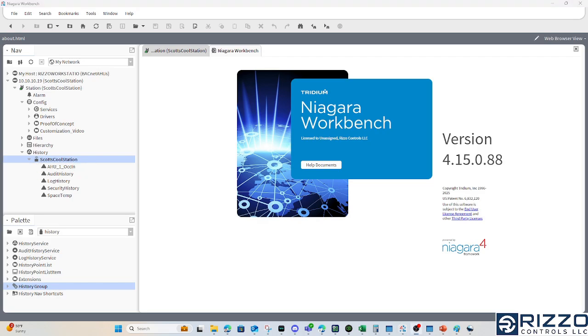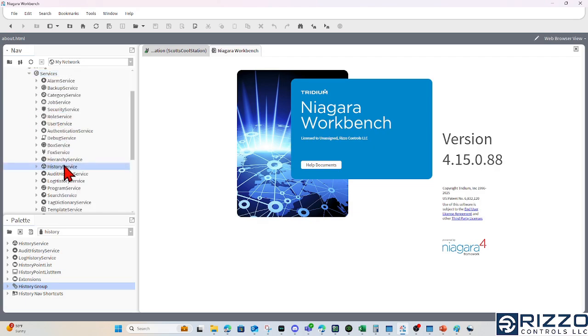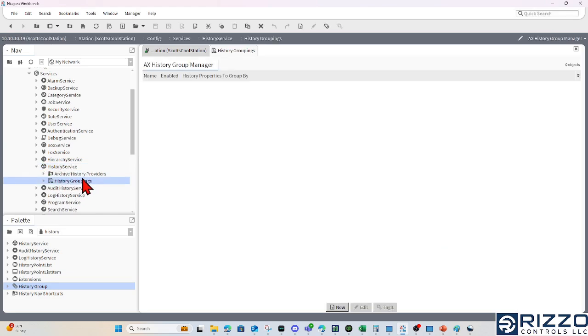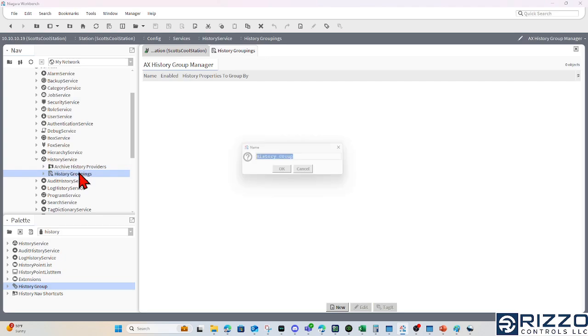So where I'll begin in this video is first creating a history group. I'll expand my services under my config space. I'll find my history service and expand that, and I'll double click my history groupings. What I'm going to do here is actually click and drag from my history palette sidebar. There's a history group, and I'll click and drag history group over the history groupings, and I'll name this something like AHUs. I'll click OK, and great, there's this AHUs group.